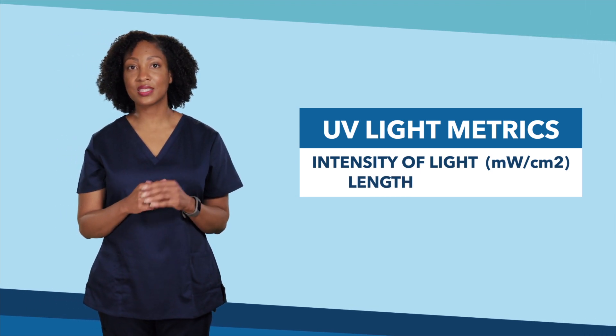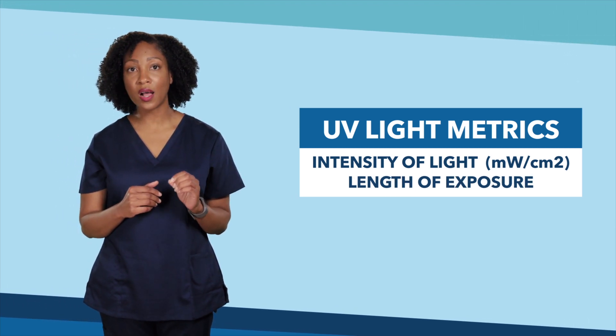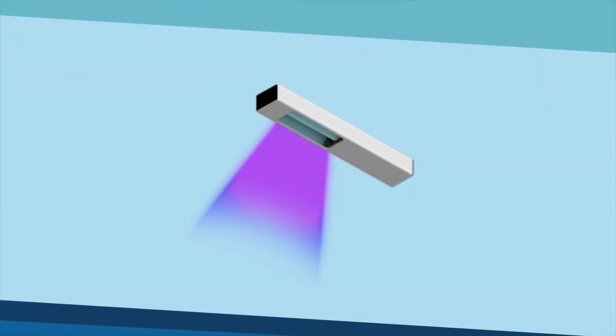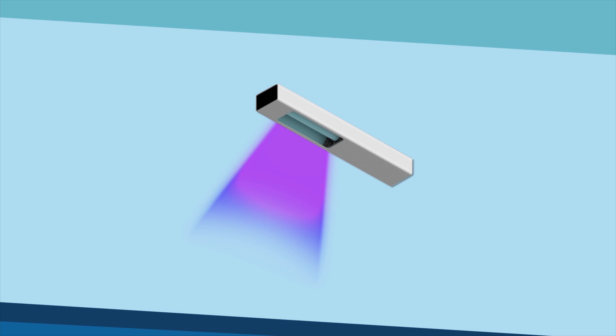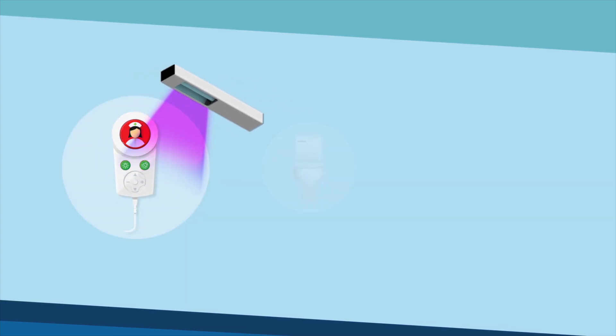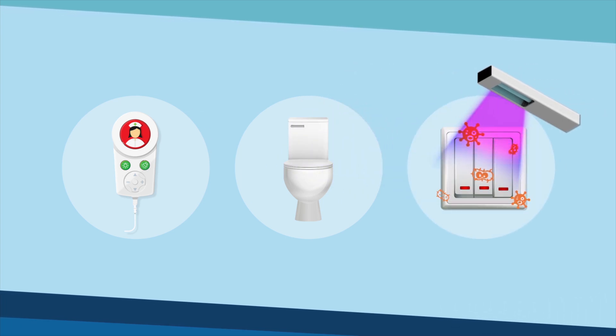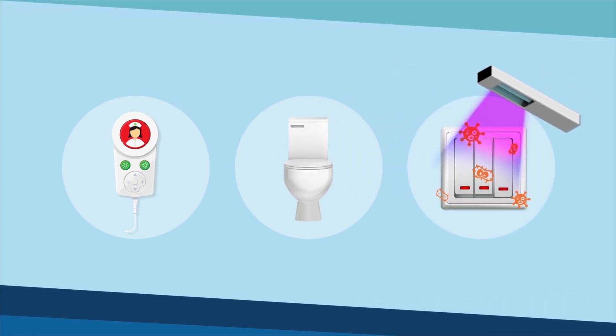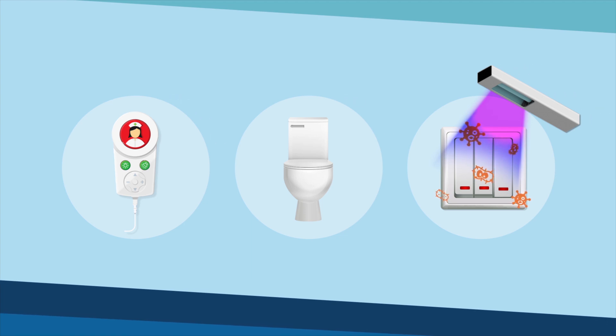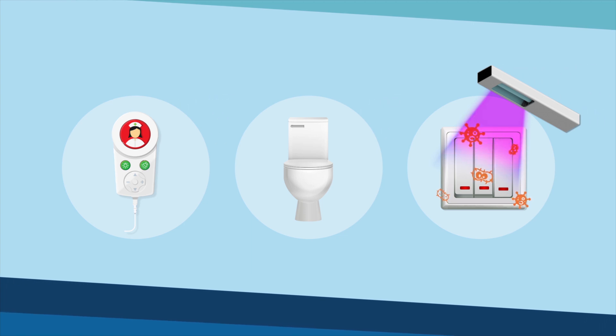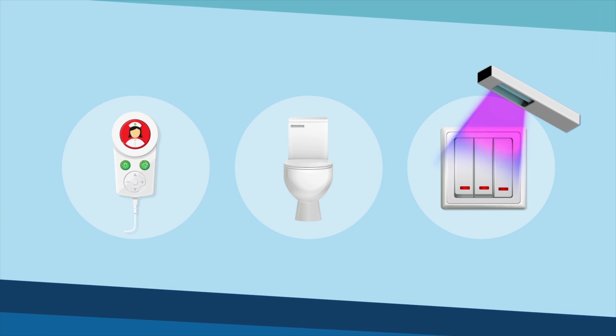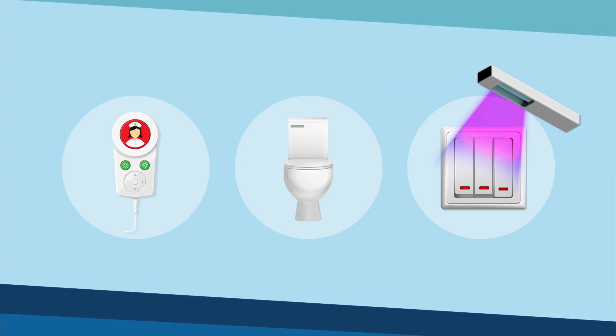The second metric is the length of exposure time, or how long the light shines on the germs. UV lights disinfect by killing everything on a surface. Whether the surface is a nurse call pillow speaker, a toilet handle, or a light switch, the germs must come into direct contact with the UV light for enough time — based on the intensity of the specific light — to be killed. Materials like dirt and dust can block the UV light, preventing it from killing germs.